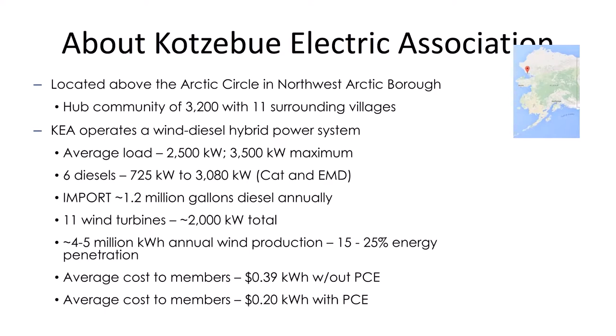Right now we're importing about 1.2 million gallons of diesel. Prior to using renewables, without them we'd probably be at about 1.4 to 1.5 million gallons. We're down to 11 wind turbines that are able to produce about 2 megawatts total. We previously had 19, and I'll talk about why we're down to 11. Our annual energy production from wind is about 15 to 25% of our annual energy production, so about 4 to 5 million kilowatt hours we're producing from wind annually at this point.